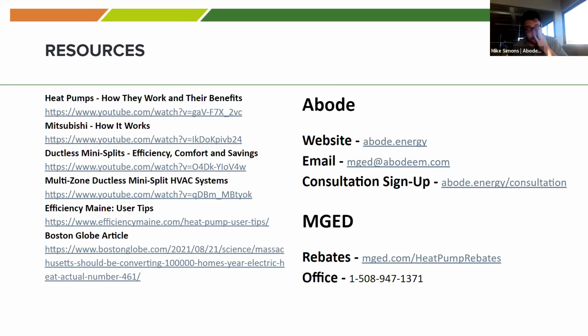So it really does depend on the load of the home. Say there is a centralized oil-fired furnace down in the basement, and let's just say hypothetically the house is a 2-story colonial, and there is a heat load of 80,000 BTUs per hour. The largest centralized cold climate ducted heat pump is around 55,000 BTUs. So there's a difference between what the home needs and what that heat pump can put out. So there's 2 thoughts to this.